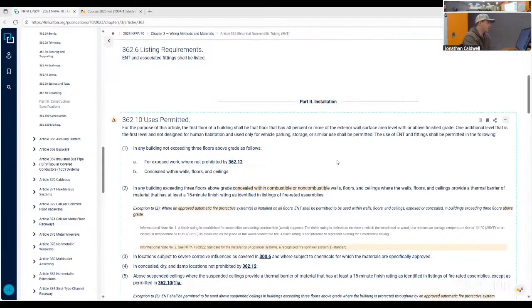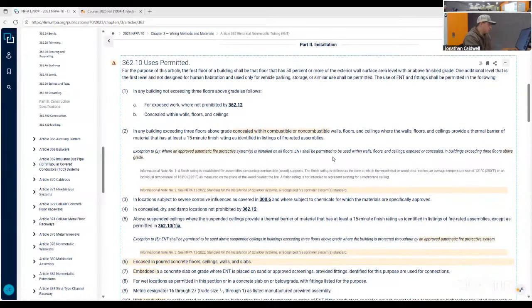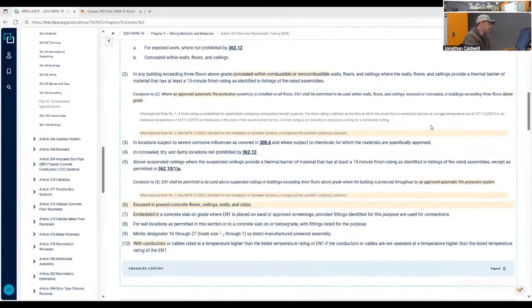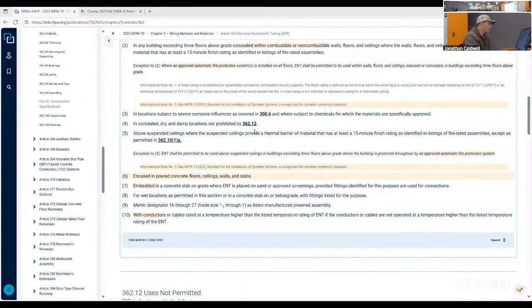Use is permitted in any building not exceeding 3 floors above grade as follows. For exposed work, not prohibited. And then concealed within walls, floors, and ceilings. In any building exceeding 3 floors above grade, concealed within combustible or noncombustible walls, floors, and ceilings, where the walls, floors, and ceilings provide a thermal barrier of material with at least a 15-minute finish rating as identified in listings of fire rated assemblies. And then here's an exception. In locations subject to severe corrosive influences as covered in 300.6, in concealed, dry, and damp locations not prohibited, and above suspended ceilings where the suspended ceilings provide a thermal barrier.